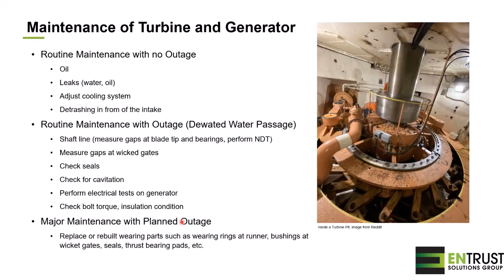The maintenance of a turbine and generator, we can divide maybe into 3 categories. So there's the routine maintenance that we do when the turbines are operated, so it doesn't require any outage. In terms of oil, we will need oil filtration, for example, check the oil levels, change oil from time to time. Usually we'll wait for an outage to change the oil. We'll check for leaks. As I mentioned, there's frequently water or oil leaks. We will need to adjust the cooling system, make sure the cooling systems are clean. And what is really important, especially for smaller projects, is to detrash in front of the intake. Otherwise, the intake will start to be blocked and the pressure differential from one side of the intake to the other side will increase, and that will reduce significantly the amount of power that can be produced.